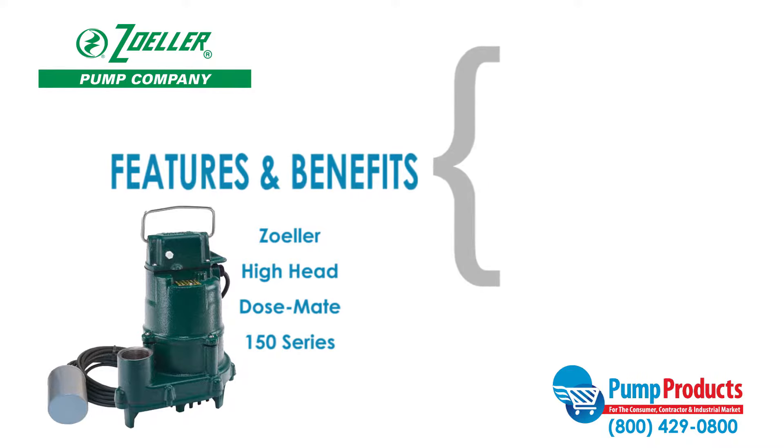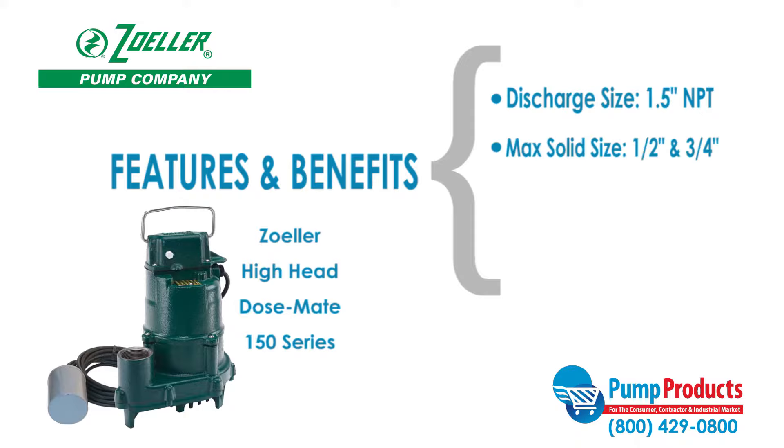Some features and benefits of the Zoeller 150 series include a discharge size of one and a half inches NPT, a max solid handling ability of half an inch for 151 models and three-fourths of an inch for 152 and 153 models, maximum capacities of 77 gallons per minute, and a maximum head of 44 feet.